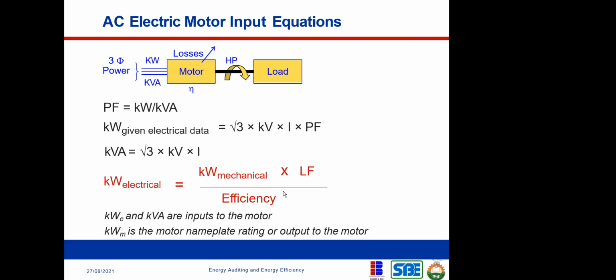When you look at the nameplate of your motor, you are always given the efficiency rating. They will tell you the kilowatt mechanical at a certain efficiency. There's no motor that is 100% efficient, so they might say a certain kilowatt mechanical at 90% efficiency. The load factor depends on the load that you're giving to it, so you need to know what load is given to that motor. The higher the load, the higher the efficiency.